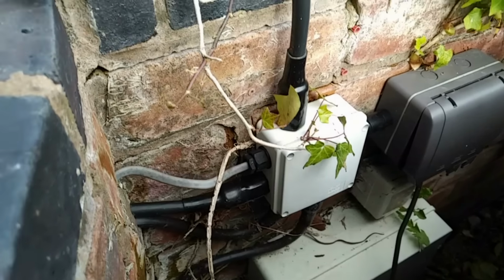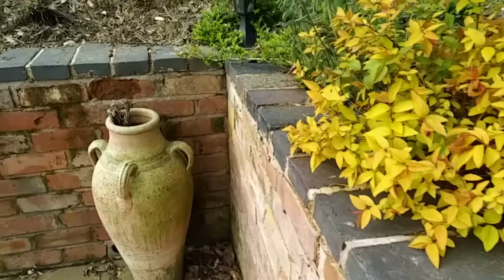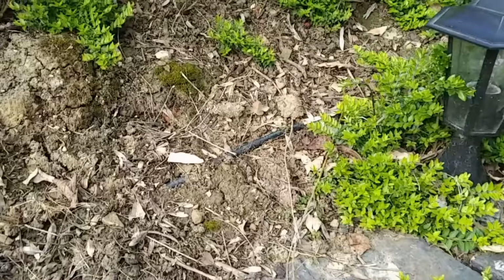We've got armoured spidering off everywhere. We've got SY cable on view. We've got going on here, there's more armoured just under the surface here. I mean, it's everywhere in this place. This looks like the work, not of an electrician, but perhaps of a landscaper who thinks he knows what he's doing, but doesn't, and has just shoved something in that has worked for a certain point and then gone horribly wrong. Let's have a look at some of these accessories.